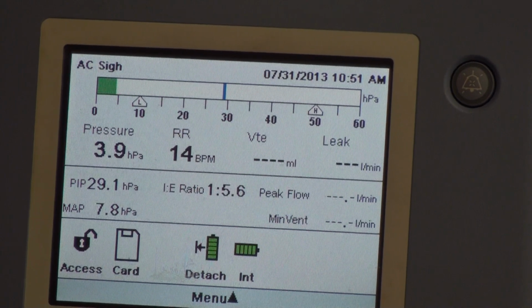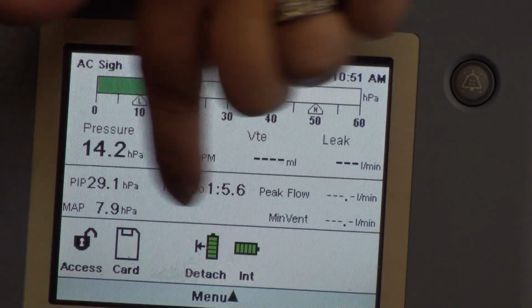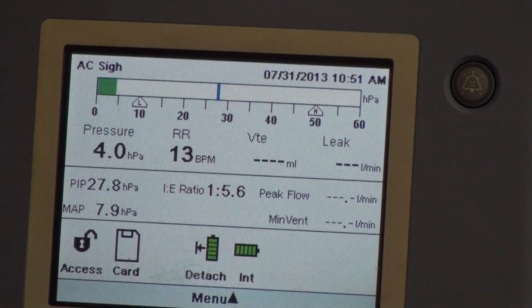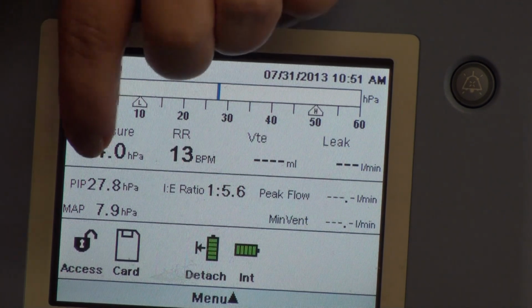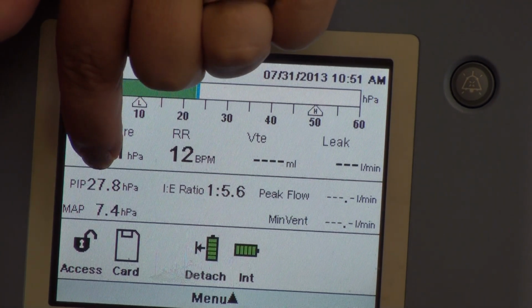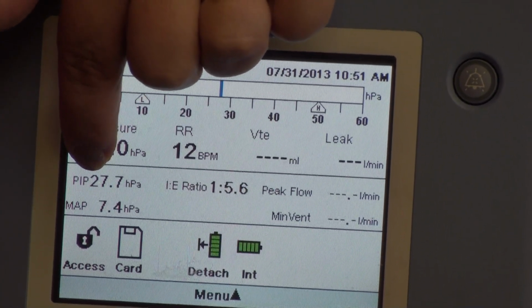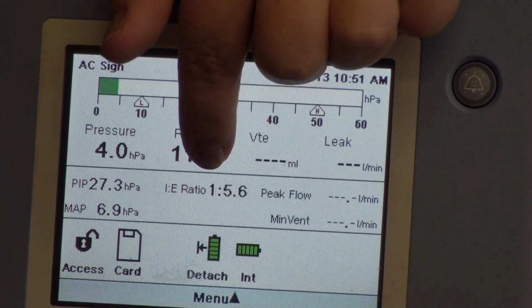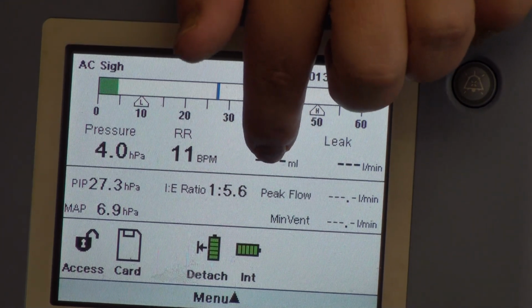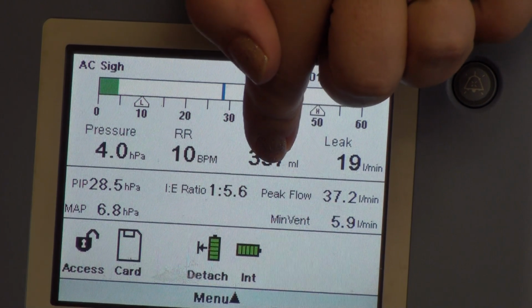All right, let's go to the next section here, which is called my measured settings panel. First of all, you're going to have your peak inspiratory pressure. Okay, and we've already talked about all these terms, so we know what these are. My peak inspiratory pressure is going to be here. B is going to be my IE ratio, so my 1 to 5.6 in this particular case. The next one's going to be my peak flow, which is the maximum inspiratory flow delivered to the client during the previous breath. Okay, so it's always a breath behind.